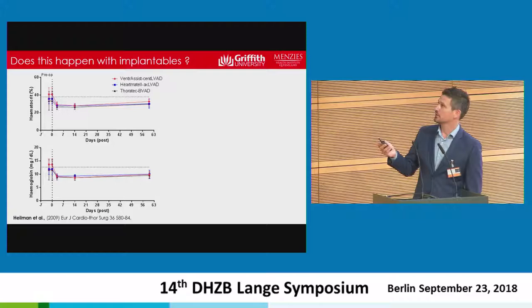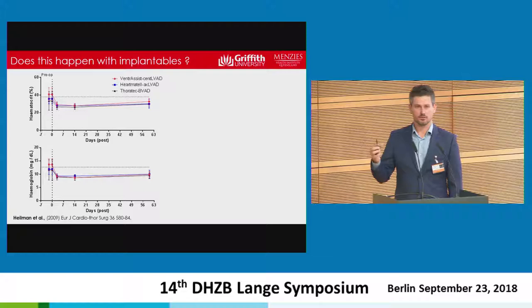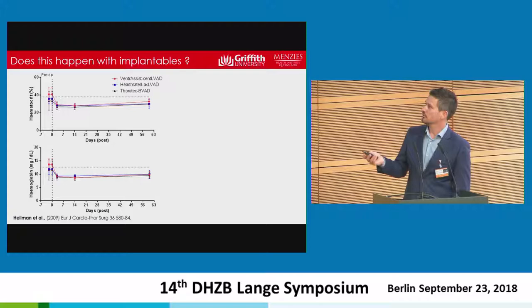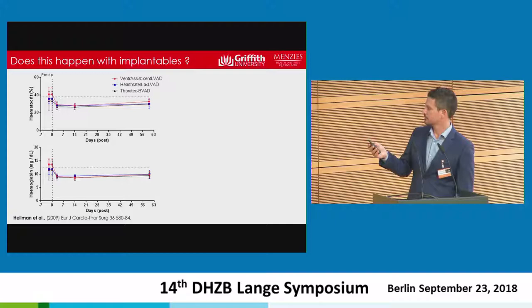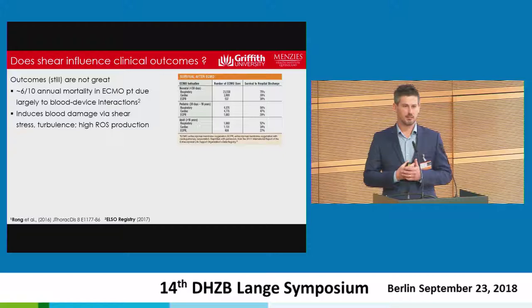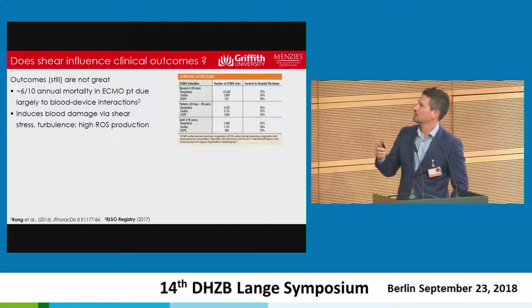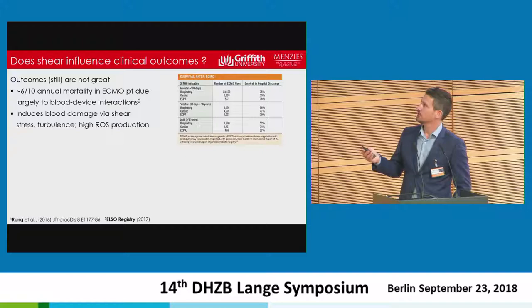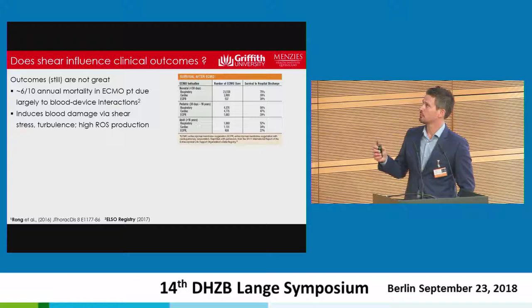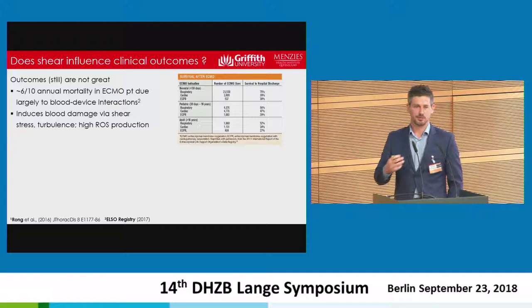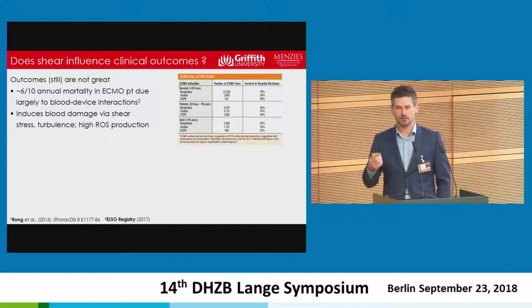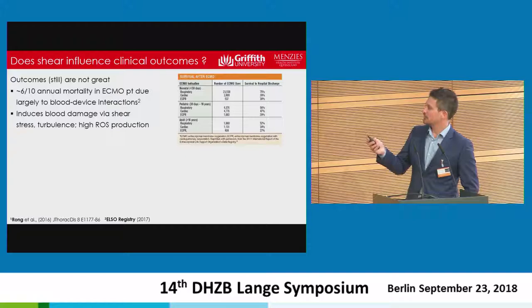Looking at what happens in vivo with implantables, across a variety of different blood pumps, within the first three days of implant both hematocrit and hemoglobin content substantially reduce, and this continues out to about 60 days. Does this have any clinical influence? Yes — ECMO patients are probably the most extreme population receiving mechanical support, and only about four in ten patients on prolonged ECMO actually survive to discharge. Looking more globally at blood pump use, freedom from adverse events is about one in ten patients within 12 months. We have a long way to go with respect to blood pump design.